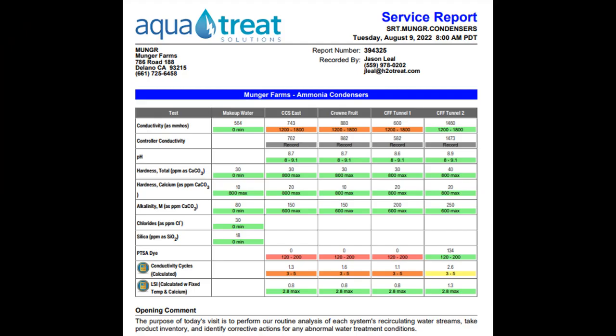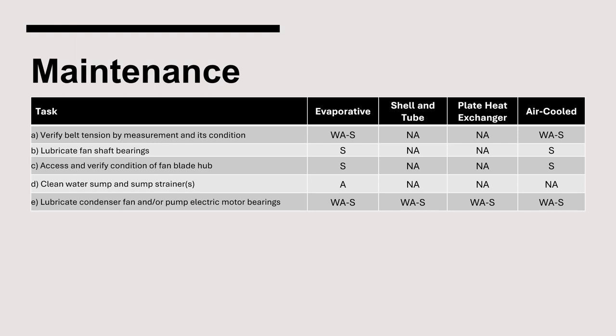Here we see an example of a condenser water treatment report from AquaTreat Solutions. Maintenance requirements of condensers include several items for the fans like verifying fan belt tension, lubricating fan shaft bearings, and verifying the condition of the fan blade hub. Sump cleaning should be performed for evaporative condensers on an annual basis. Lastly, condenser fans and pump electric motor bearings must be lubricated.